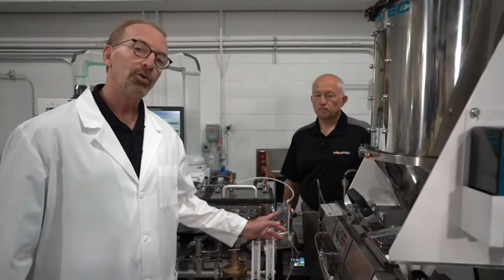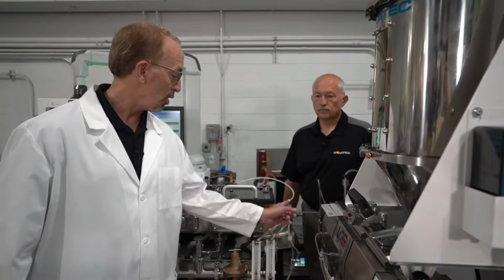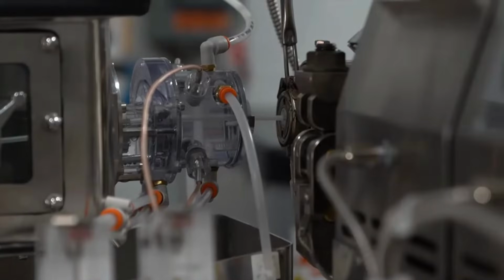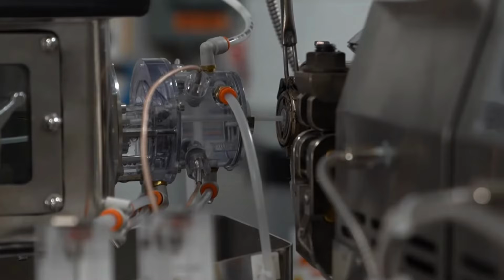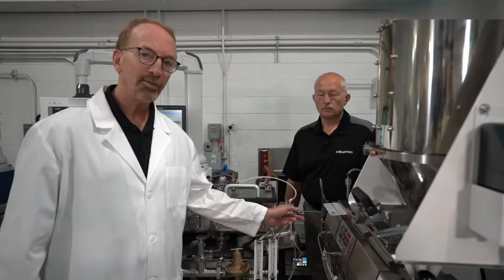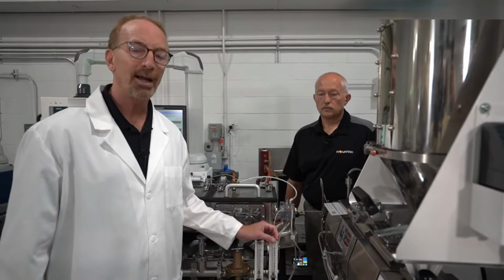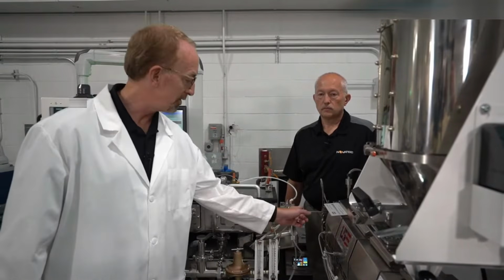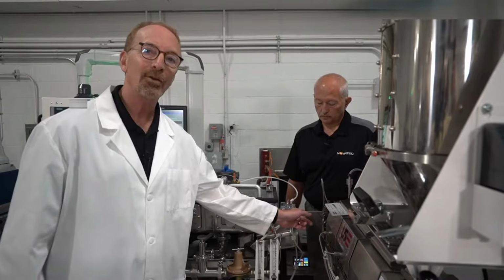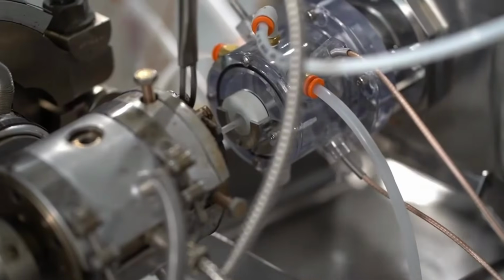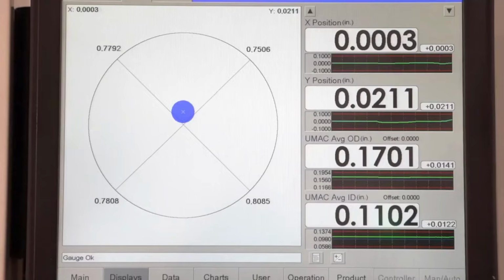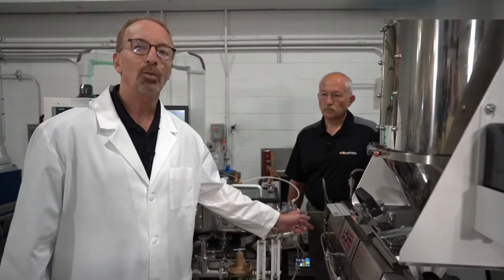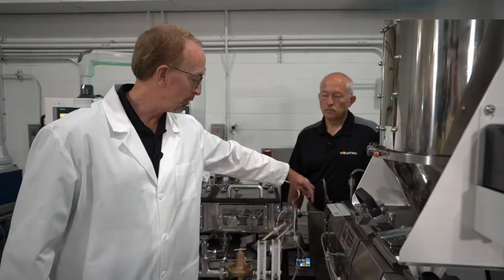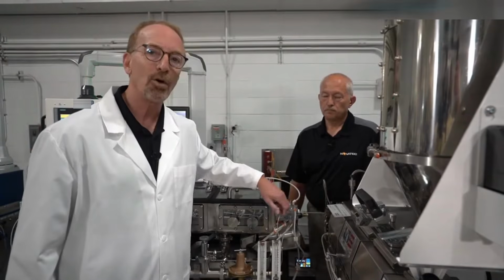And now we're going to go into a little bit further detail about what we call the transducer holder. This unit has been specifically designed with small medical tubing extrusion in mind. One of the most difficult things that processors have today is making sure that this tiny tube, and this tube could be 10 thousandths of an inch, is in the center of your tool. And for years, people have tried, can we use a camera there? And there are crossheads, and if we're right up against here, it's very difficult to see.